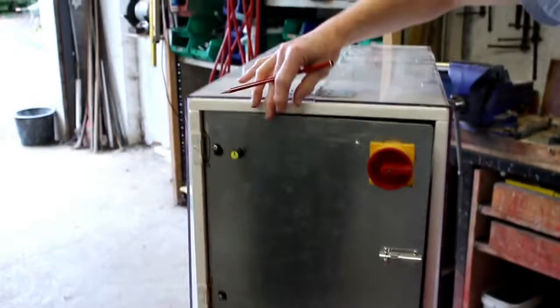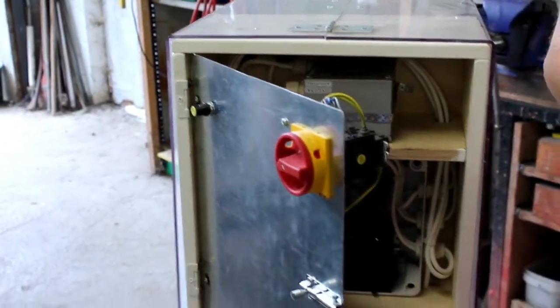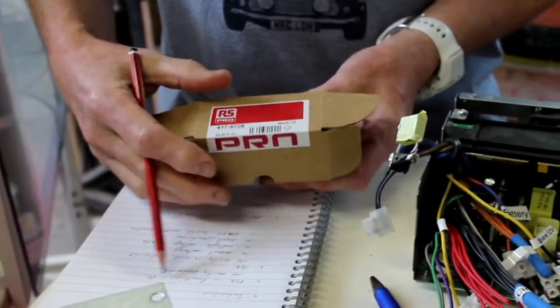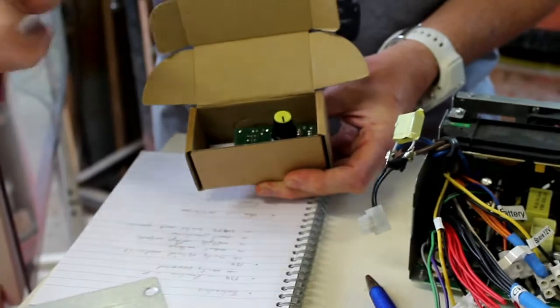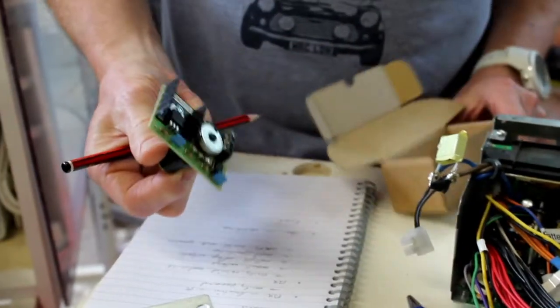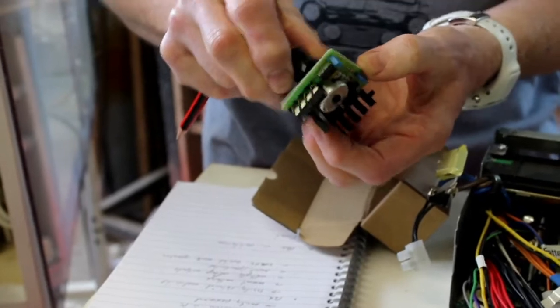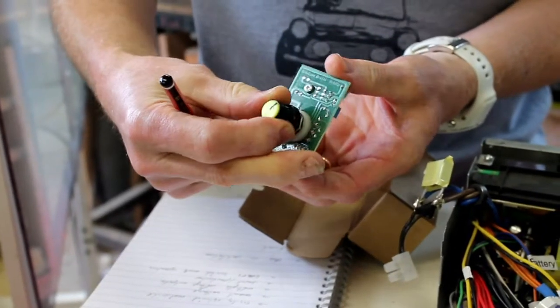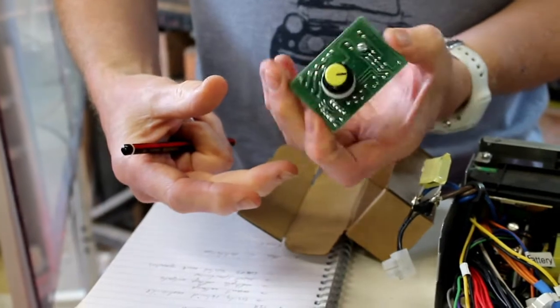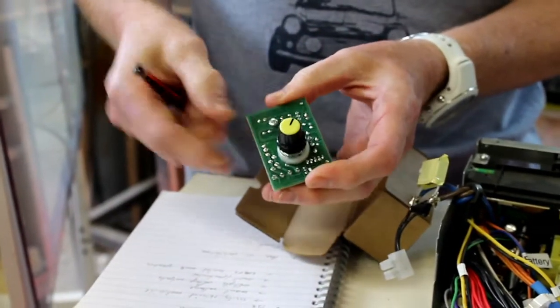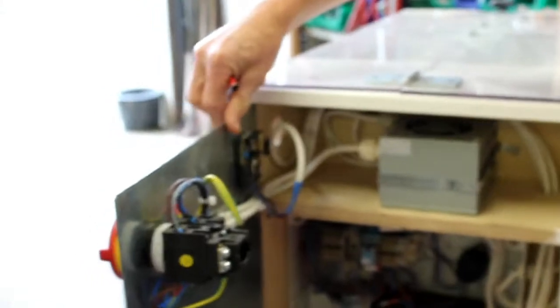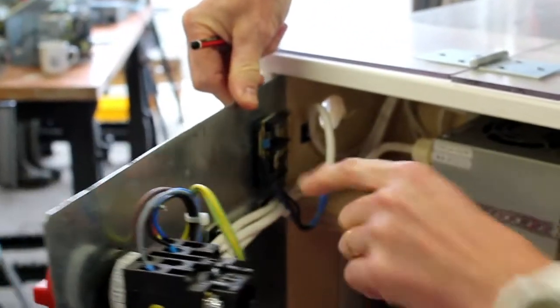There's a wee speed controller that we got from Radionics. I have one here in a box. We bought them from Radionics. They're around 20 quid or 20 euros or something like that. And this is it here. This is used to control the speed of the motor, and by controlling the speed of the motor we can control the breath rate per minute on the ventilator. And so that's it located here on the front door of the cabinet here.